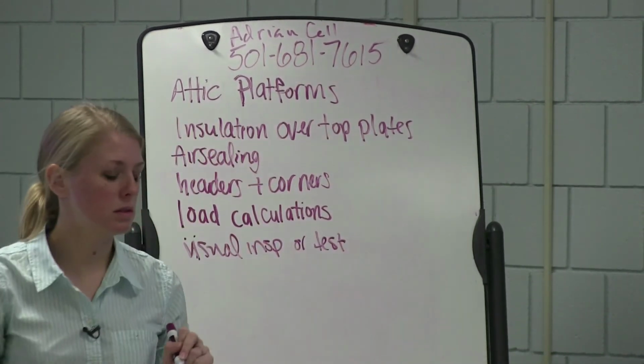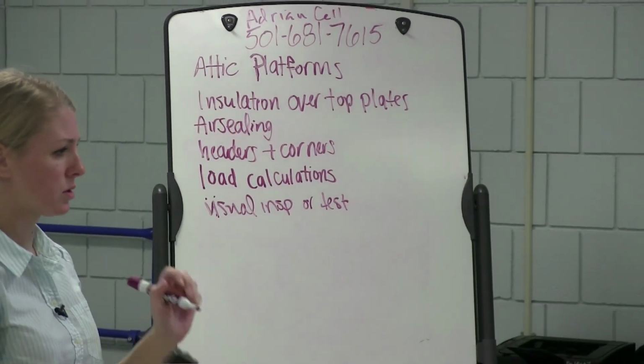And then duct sealing, is that another thing that was sort of? Kind of where we're going with that is the fact that we're requiring either a mastic paste or a mastic tape to seal the ductwork. On that issue, we've got on number 3, attach the inner liner of flexible duct with nylon plastic straps and tighten with a manufacturer-approved tool. In the 30-page document that is the Arkansas changes to the international code, it states that even the flex duct needs 3 screws, just like the metal duct does.